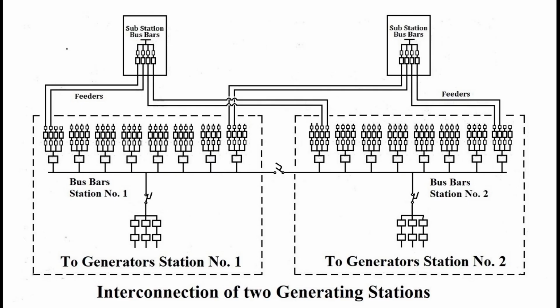Shown here is an example of the segregation concept. Two generating stations are shown, with others not shown, interconnected in a similar manner. If station number 2 has been taken offline by a fault, its disconnect is open, and the interconnection switch is closed. This would allow some of the load on station number 2 to be supplied by station number 1. The entire load of station number 2, however, would be too much of a demand for station number 1. In a similar manner, during a failure of station number 1, its load could be switched to station number 2.